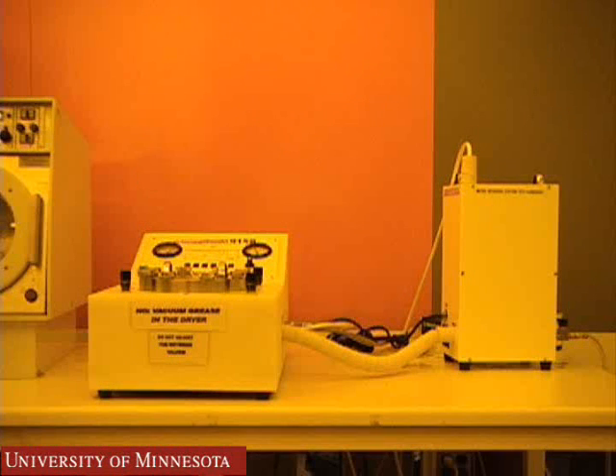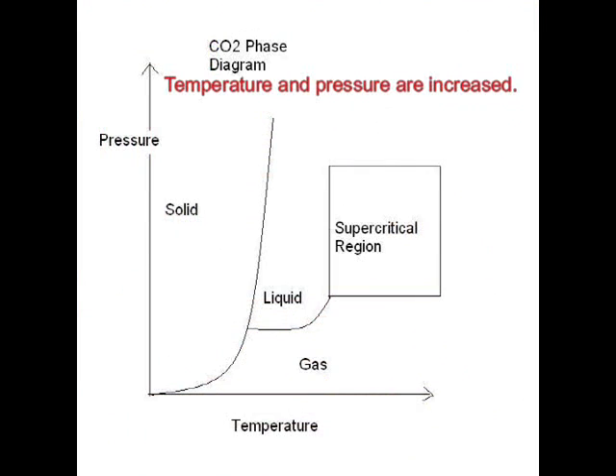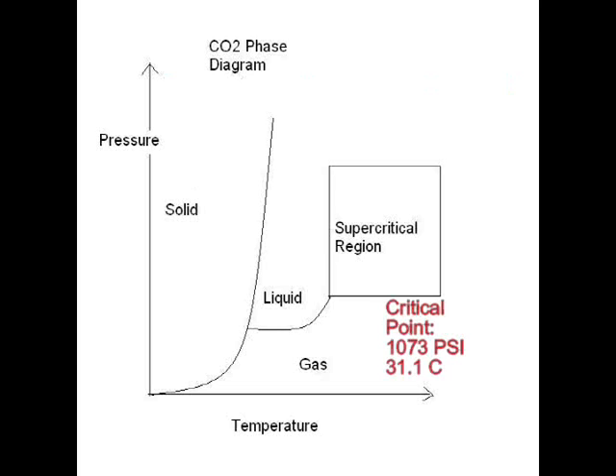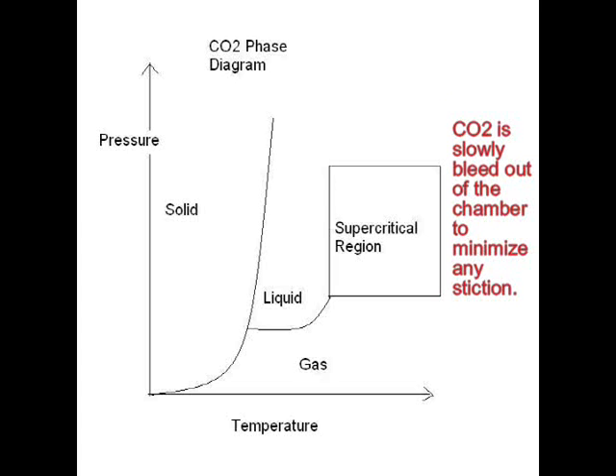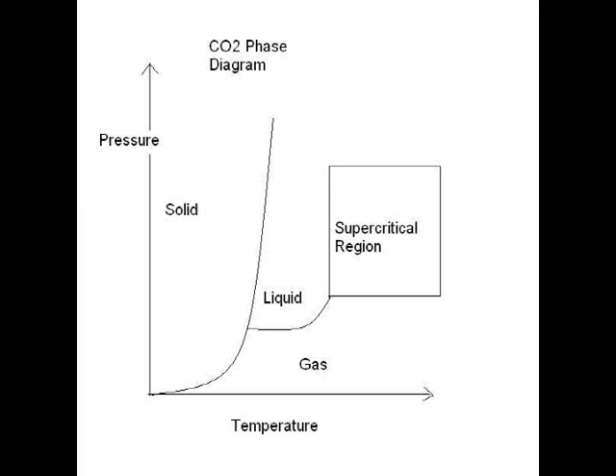The CPD consists of a chamber and a condenser to the right of the machine. Behind the CPD in the chase are two liquid CO2 tanks. The liquid CO2 is slowly increased in temperature and pressure until the supercritical region has been reached. There is no distinct difference between the liquid and vapor phase in this region. This lack of interface allows the CO2 to be slowly bled off without breaking any beams or causing stiction.